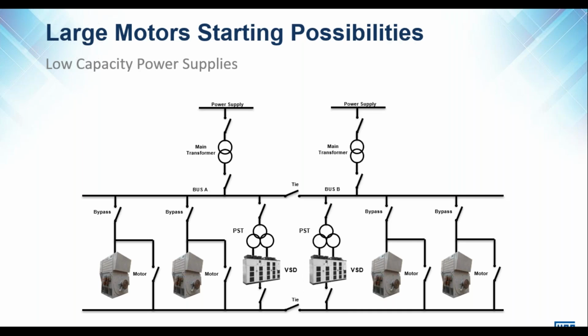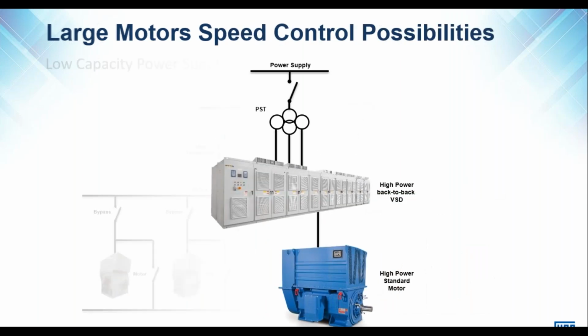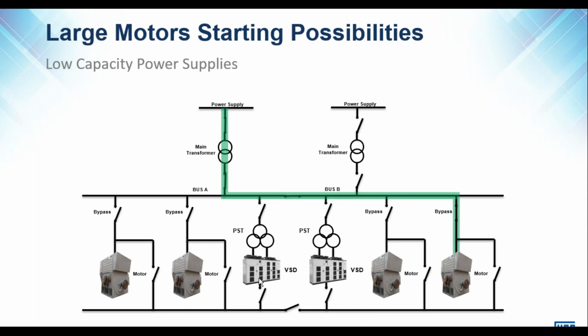We can do the same technique, but add in some redundancy, just in case there is an issue of reliability. If there's some concern there, we can do a similar control method, but putting two VSDs, just have one as a backup, in other words. So here we have an example of starting motor 1 with the VSD, bypassing that motor. And then we can use that same VSD to start multiple motors.